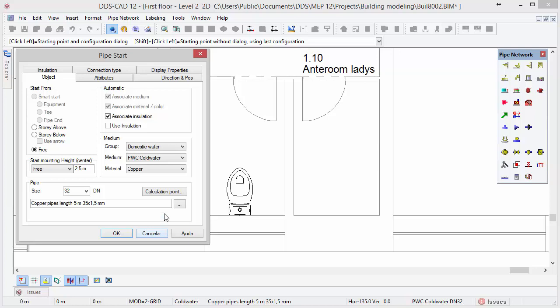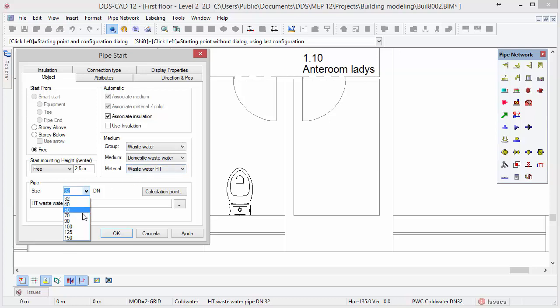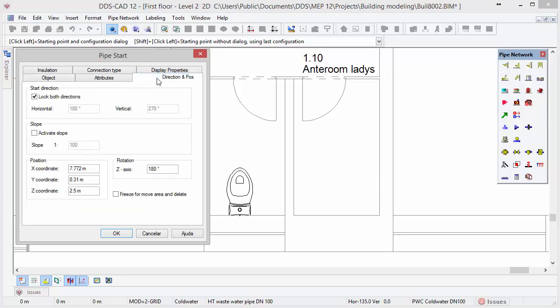In the medium drop-down list, select the type of system. In the group drop-down list, select waste water and domestic water. Since we are going to design a stack pipe, we will start with a pipe size of DN100. In drainage it's important to configure the slope of pipes so that water runs in the right direction. Go to the tab Direction and Position, and at Slope you can activate it with a checkbox. DDS-CAD considers a default slope of 1 to 100 which you can edit if required. Press OK to close the dialog.